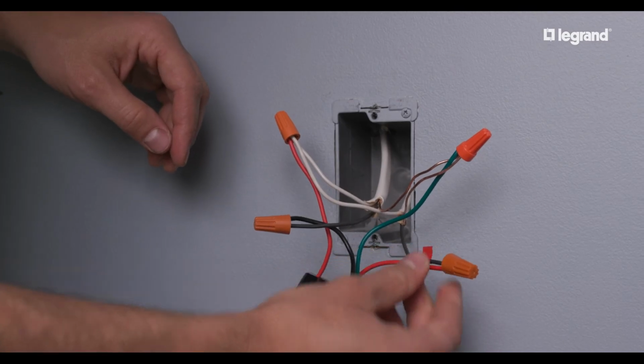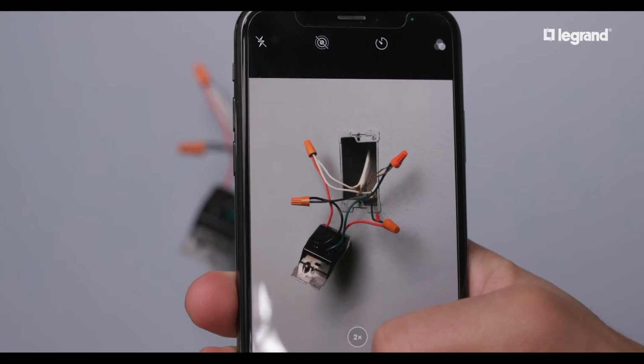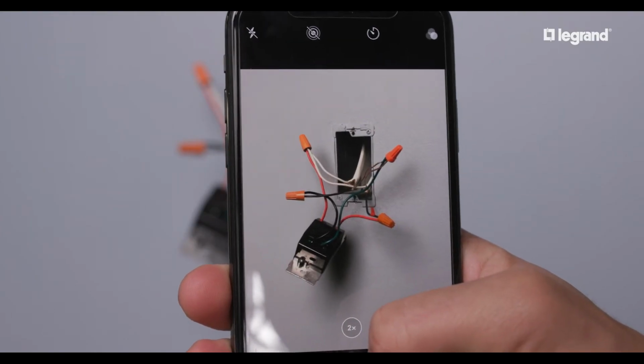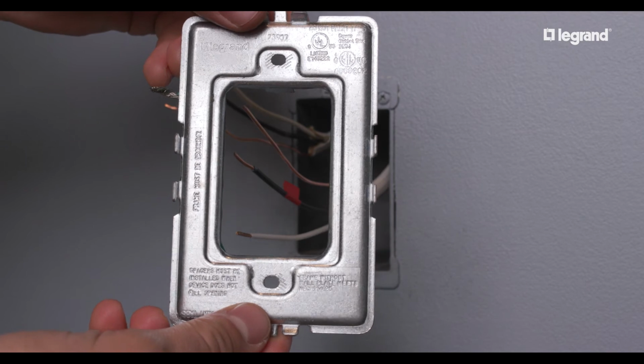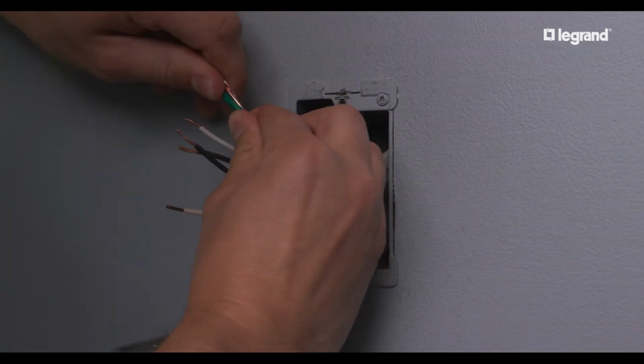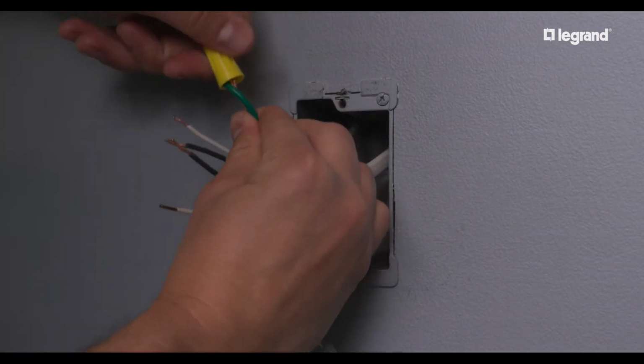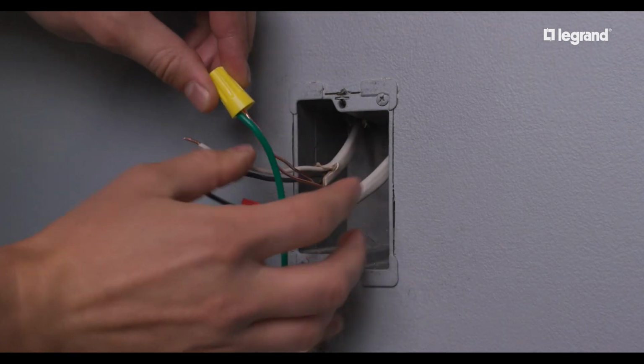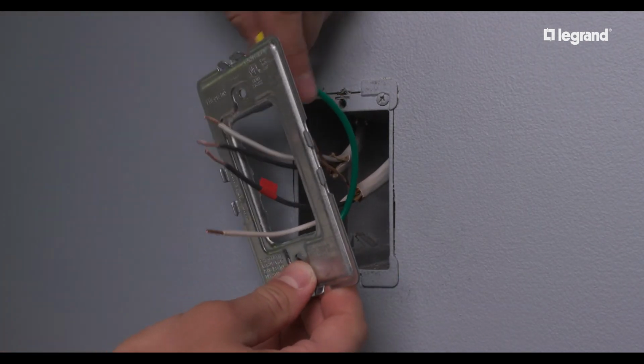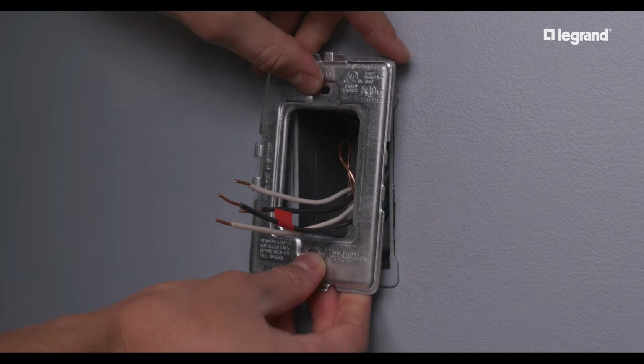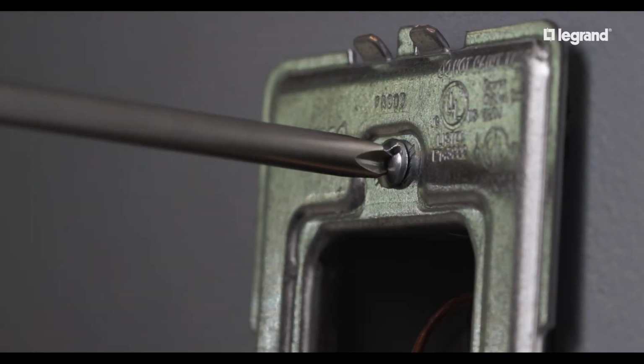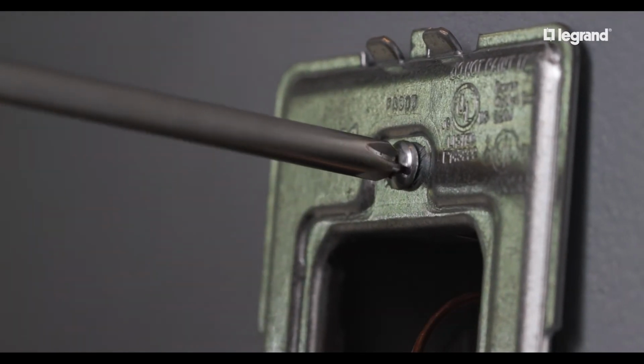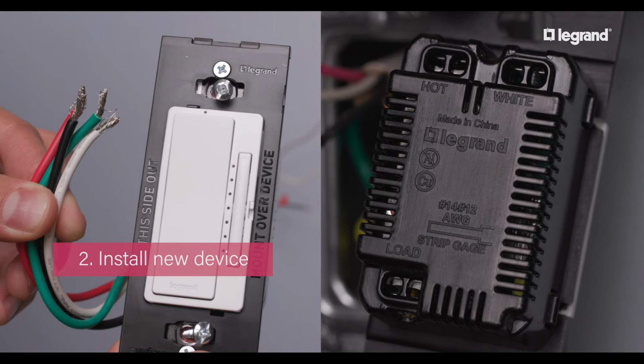Before removing the old device, it may be helpful to take a quick photo of how it's wired to refer to later. If installing an Adorn switch, connect the green ground wire from the metal frame to the ground wire in the box. Gently fold the ground wires into the box. Attach the frame with the provided screws, tightening it just enough to hold it in place. Do not over-tighten. Depending upon the device you are installing, you'll either connect wire to wire or wire to terminal.